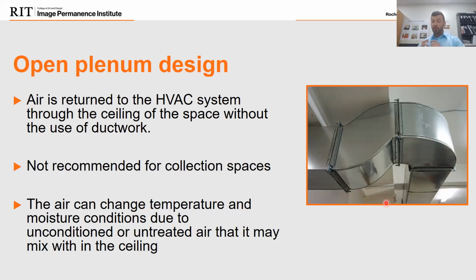So the air comes to your room in ductwork, is distributed to your collection space, and then when it leaves the collection space, we want to see it leave within ductwork as well. All too often when we see issues within collection space, that's because the air goes up into the ceiling and mixes with air from wherever. It can collect dust, and as it moves back to the unit, the condition can significantly change because of that open plenum design.